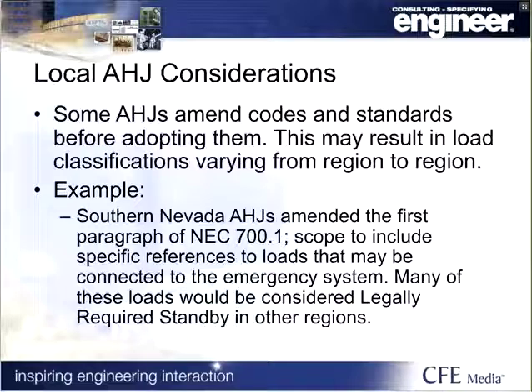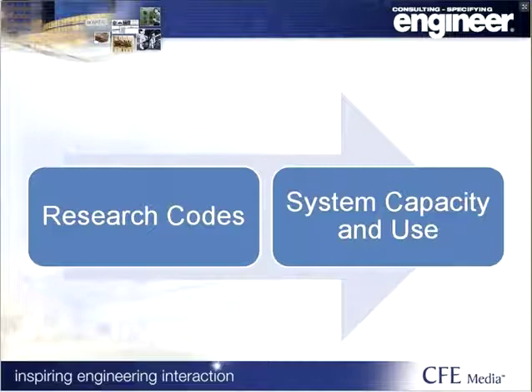Many of these loads are considered legally required standby in other regions, such as smoke evac systems, elevators in high-rises, lighting and power in the fire command center, and HVAC systems that serve emergency and electrical rooms, as well as elevator machine rooms. And now I'll turn it over to Jim to continue.